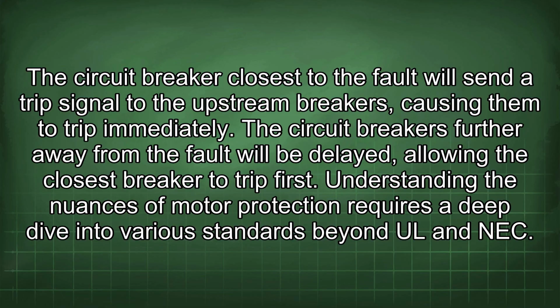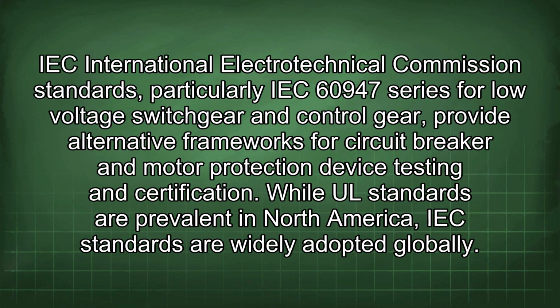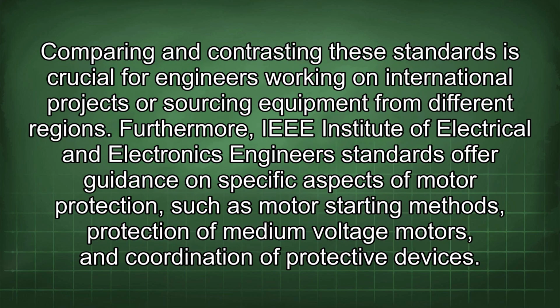Understanding the nuances of motor protection requires a deep dive into various standards beyond UL and NEC. IEC (International Electrotechnical Commission) standards, particularly the IEC 60947 series for low-voltage switchgear and controlgear, provide alternative frameworks for circuit breaker and motor protection device testing and certification. While UL standards are prevalent in North America, IEC standards are widely adopted globally. Comparing and contrasting these standards is crucial for engineers working on international projects or sourcing equipment from different regions.